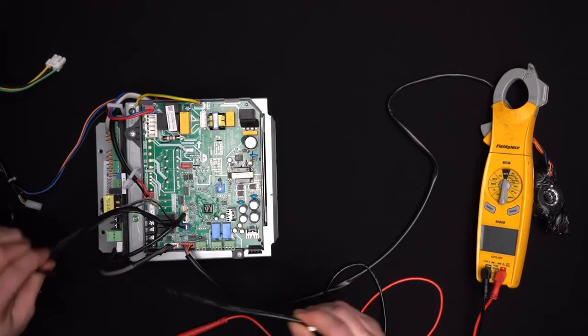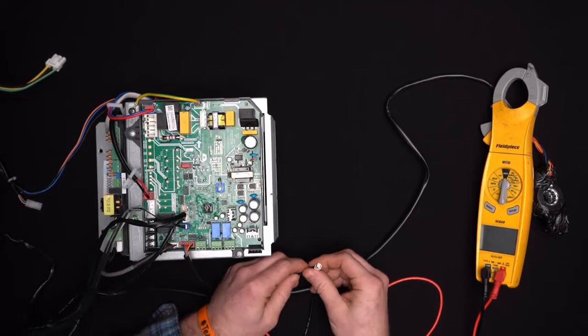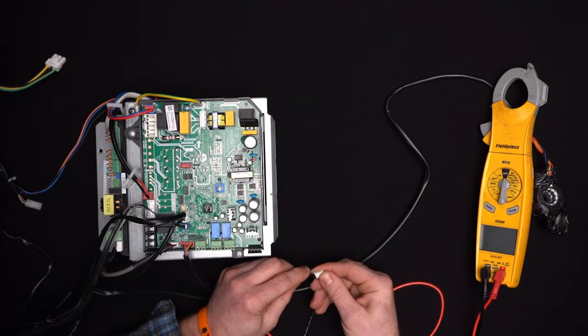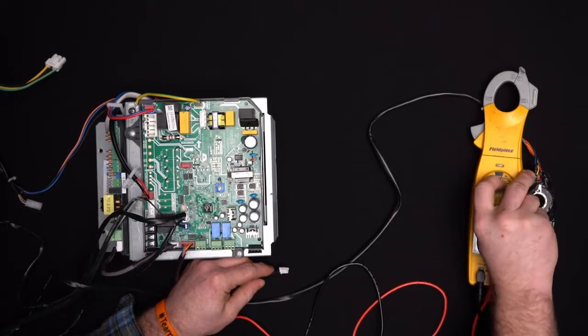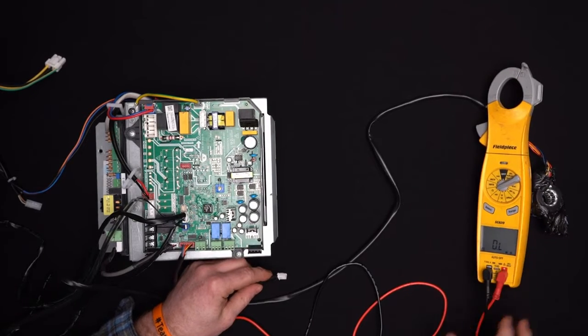We'll remove these. You'll check resistance on a thermistor. These are 10K thermistors. I'm going to set my meter to ohms.